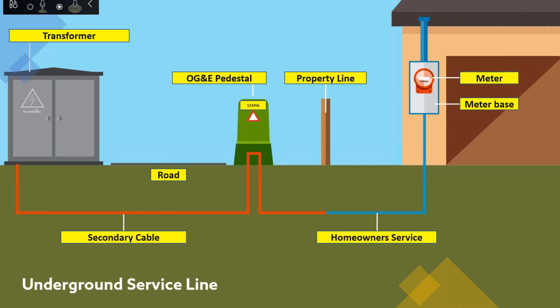We also have three-phase transformers throughout business parks, or even up to a hotel or anything that needs three-phase, and you'll find that transformer. Underneath that transformer is the secondary cable, which runs from the transformer over to this green pedestal. That secondary cable is generally about 3.5 to 4 feet below the ground. About half the time it's going to be in pipe, and the other half direct buried.